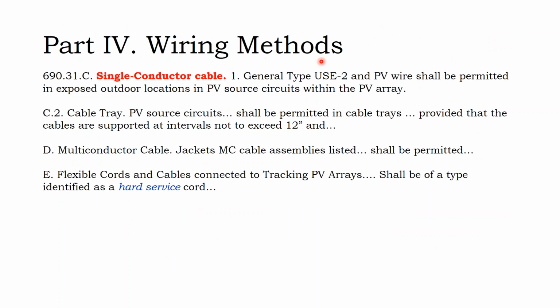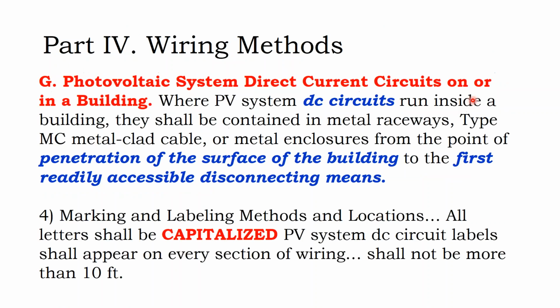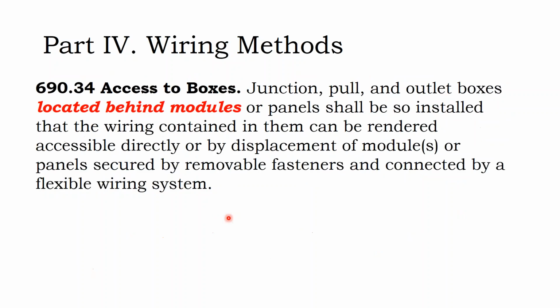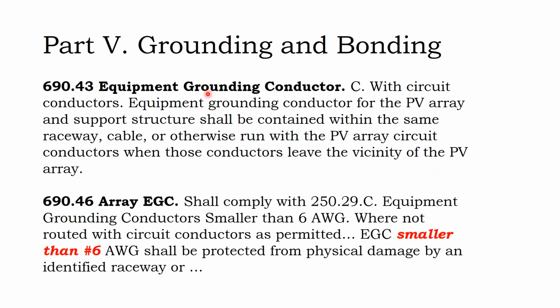This is where you're allowed to use USE-2 and PV wire for outdoor locations on PV source circuits. You are allowed to run DC circuits inside a building, but they need to be contained in metal raceways. Capitalize your letters on your warning labels. The junction boxes are allowed to be located behind the solar modules on your rooftop. So an inspector might tell you, no, they have to be accessible, so they can't be hidden underneath the array. That's not true.